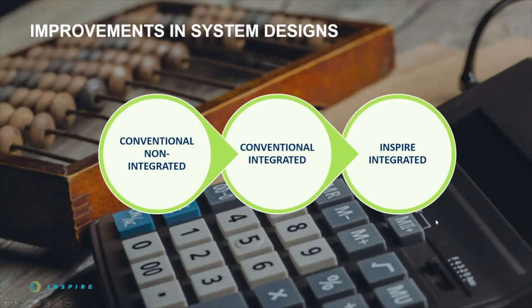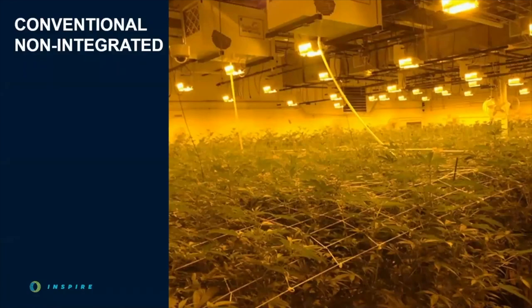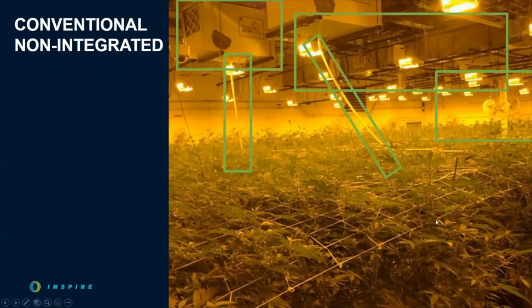Let's start with the conventional non-integrated design approach. Just by looking at this picture, you can recognize this system type because it has a pretty glaring feature: hanging from the ceilings are dehumidifiers. The primary HVAC system that you don't see in the room is most likely a commercial system, probably designed for regular commercial or office building type loads. We're used to seeing mini-splits or off-the-shelf package rooftop units serving these rooms. This is why we call it a conventional system — it just can't handle the humidity levels required for a cultivation space alone. Hence, we have all these de-hums installed in between the lights.